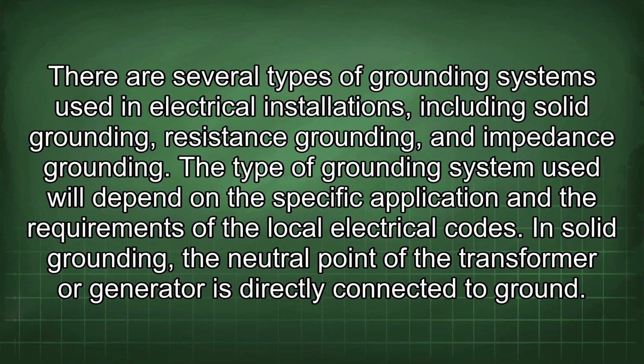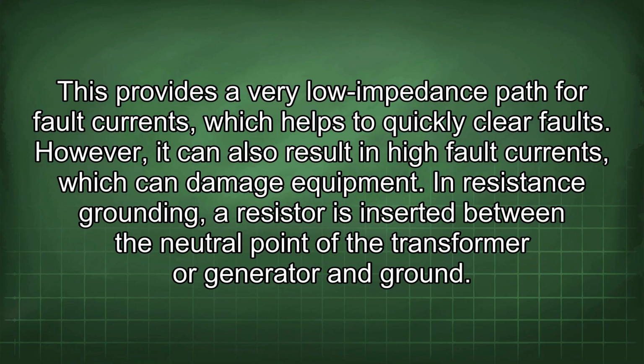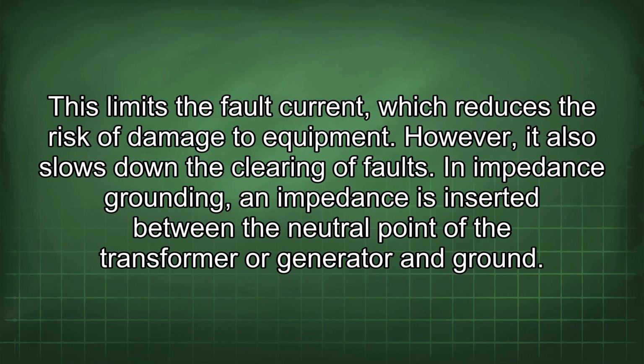In solid grounding, the neutral point of the transformer or generator is directly connected to ground. This provides a very low impedance path for fault currents, which helps to quickly clear faults. However, it can also result in high fault currents, which can damage equipment. In resistance grounding, a resistor is inserted between the neutral point of the transformer or generator and ground. This limits the fault current, which reduces the risk of damage to equipment. However, it also slows down the clearing of faults.